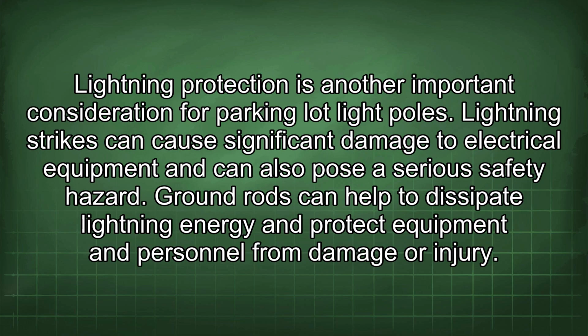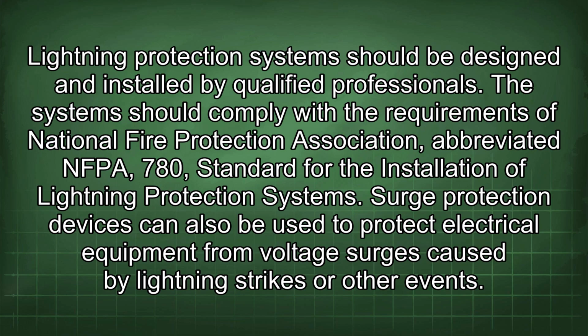Lightning protection is another important consideration for parking lot light poles. Lightning strikes can cause significant damage to electrical equipment and can also pose a serious safety hazard. Ground rods can help to dissipate lightning energy and protect equipment and personnel from damage or injury. Lightning protection systems should be designed and installed by qualified professionals.